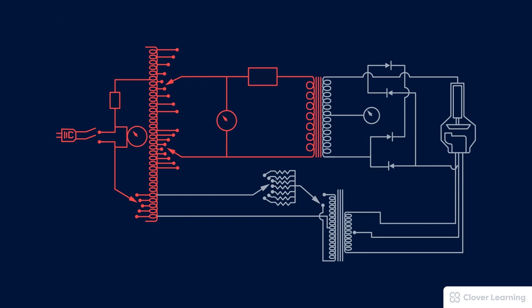The rest of the primary circuit relates to the primary exposure factors, especially the kVP. The electricity coming into the x-ray machine is 220 volts, but that's not enough to make an x-ray. In radiography, we need to use more than one voltage setting, and we need kilovolts, not just volts.